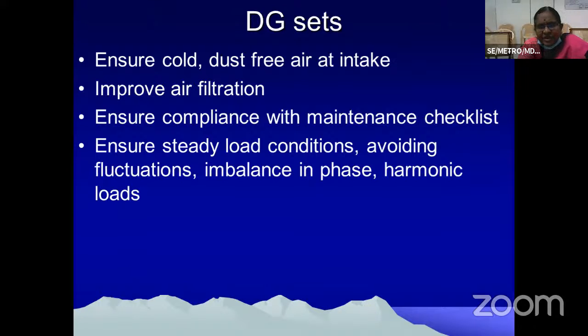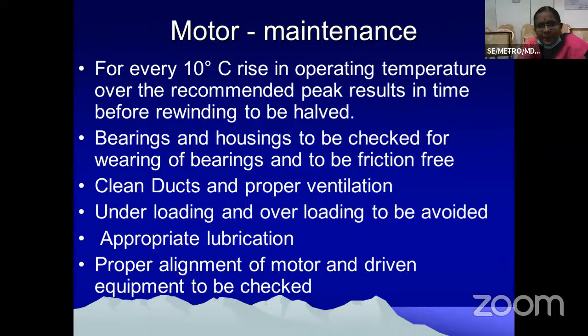Potentials of energy conservation in DG sets: ensure cold and dust-free air at intake, improve air filtration, ensure compliance with maintenance check, ensure steady load conditions, avoiding fluctuations, imbalance in phase, harmonic loads. This is with respect to motor maintenance in industries. For every 10-degree rise in operating temperature over the recommended peak, the time before rewinding is halved. Let us not use rewound motors in industries. It consumes a lot of power.